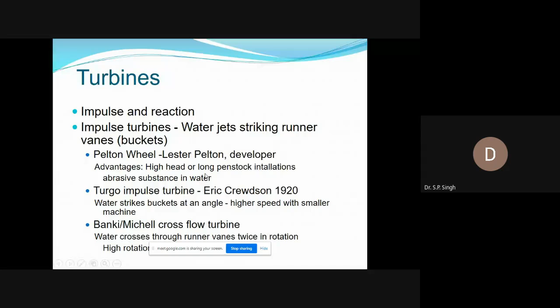Let me start with a little bit about the turbine. What kinds of turbines are there? Normally Pelton and Turgo type turbines are used, and the main issue is how to select the turbine. The basic criteria is the specific speed. For a given head and flow, we have to calculate the specific speed, and depending upon that specific speed we decide what kind of turbine to select.